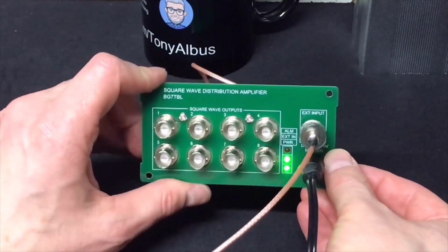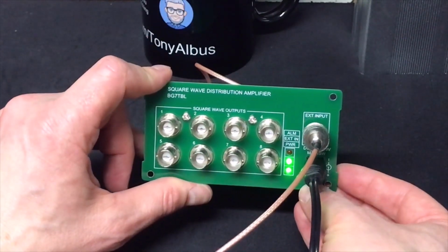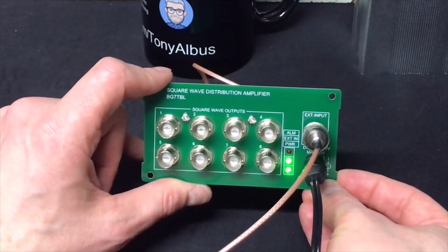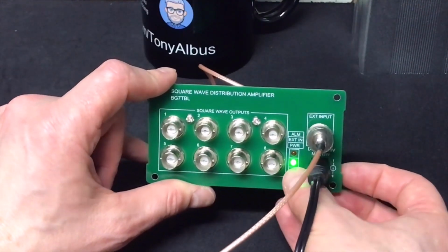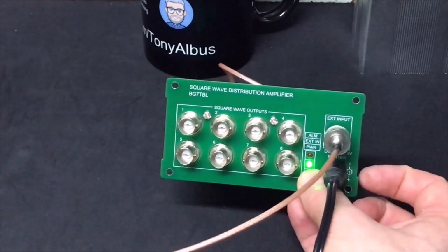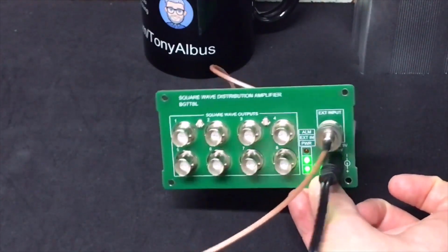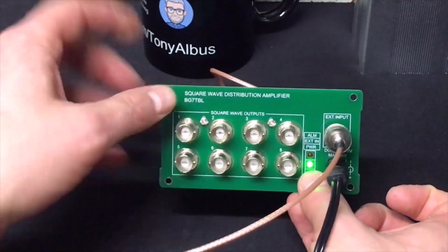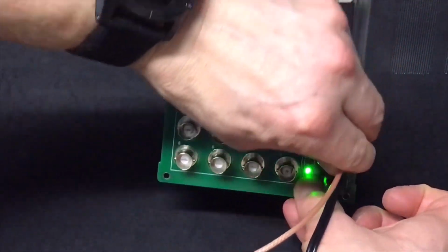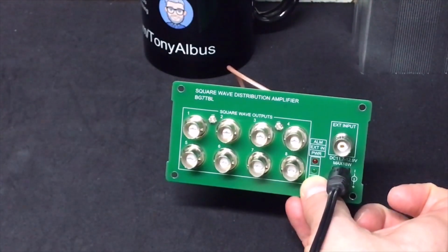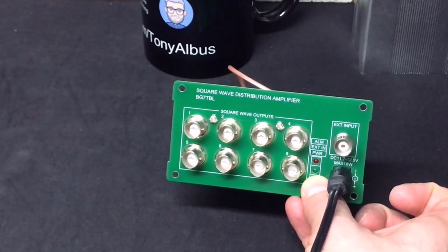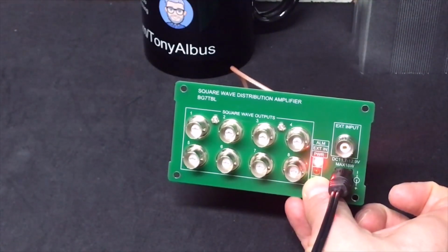So I was thinking, instead of using the power light, I just use the external in light and the alarm light, because it is clearly on now without seeing the power light, you know? Because there is a green light. And if I pull this out, after a while, it will recognize there is no signal, and then there is an alarm.